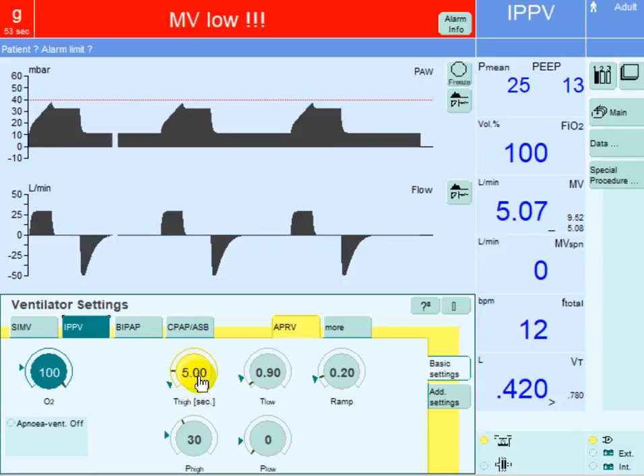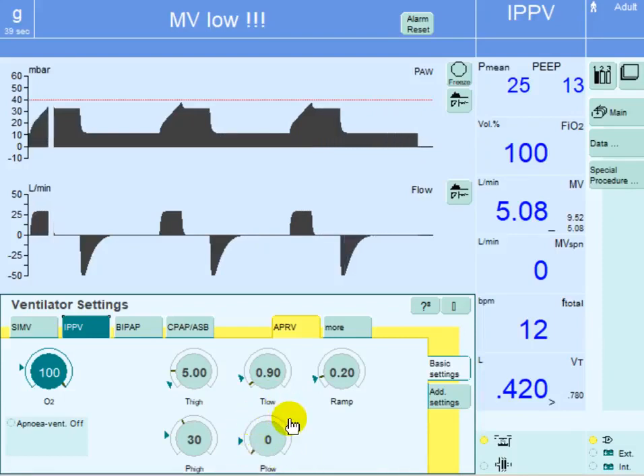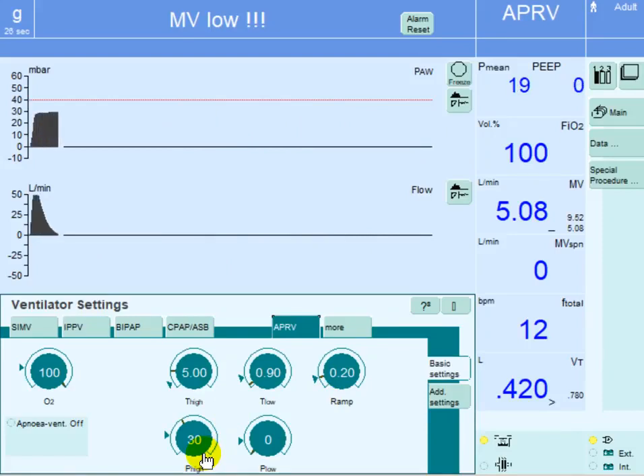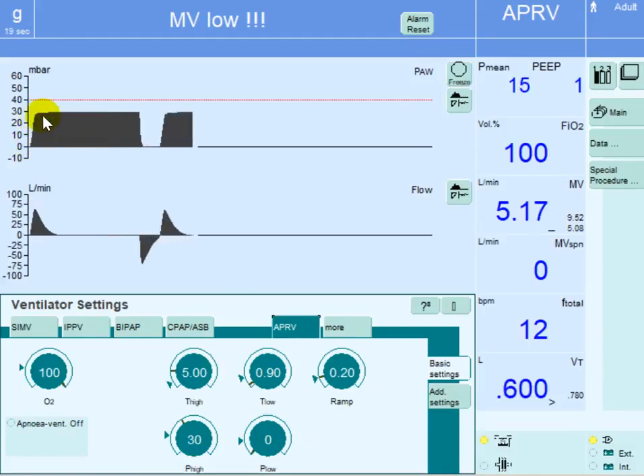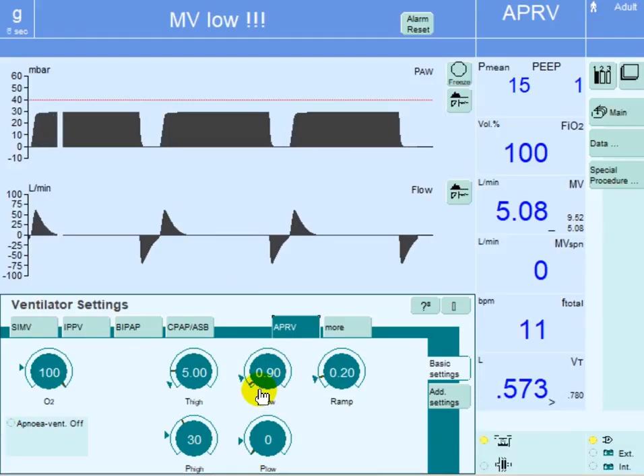We define T-high at five seconds. The P-low will be zero, to release that pressure all the way to zero, and we define the expiratory time or T-low at 0.9 seconds. So P-high is 30 centimeters of water, P-low is zero — meaning pressure goes up to 30 and then is released to zero — with T-high of five seconds and T-low of 0.9 seconds.